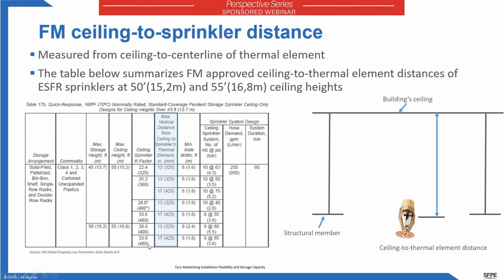At the 55-foot ceiling where there are 2 sprinklers listed, you can see the ESFR 33.6 has a distance of 17 inches. The ESFR 28 has a distance of 13 inches. So again, you have to understand the specifics around the products that you're using.